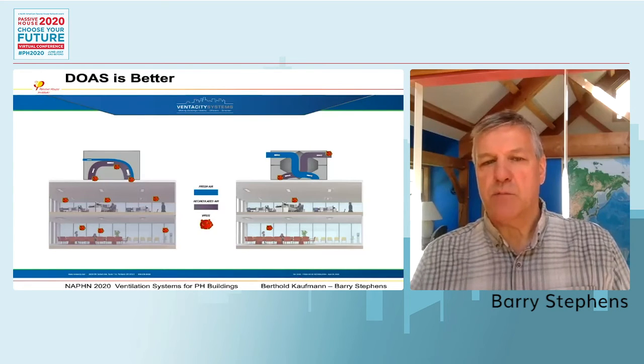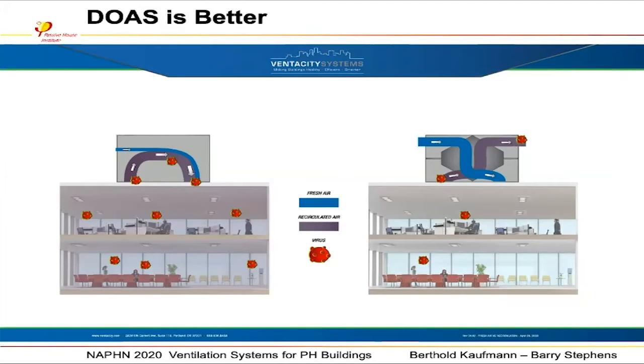Another thing that's happening is people are talking about pure ventilation with a dedicated outdoor air system, versus a lot of US and North American systems, which don't use DOAS, or dedicated outdoor air systems. They use combined heating, cooling, and ventilation systems called RTUs, or rooftop units. What you see on the left is a rooftop unit that's got a damper that brings some fresh air in. That's how they provide fresh air to the building. But the heating and cooling is done in recirculation mode. Recirculating means that you're pulling air from one part of the building and then distributing it back into the entire building or the entire zone serviced by that rooftop unit. As opposed to a dedicated outdoor air system with heat recovery, which you see on the right, where we're extracting the air directly and all of that stale air goes directly out.